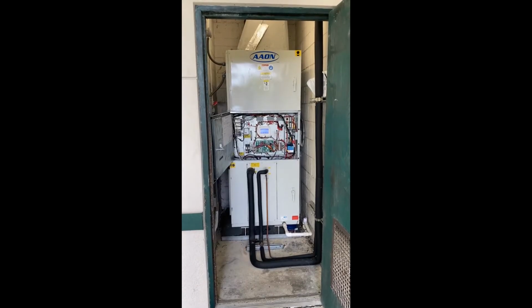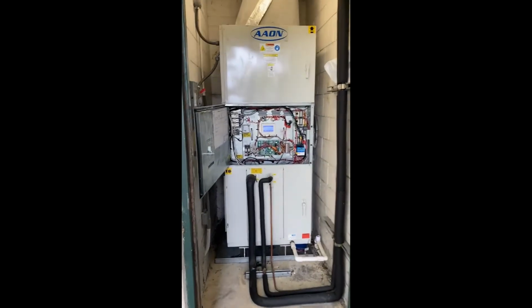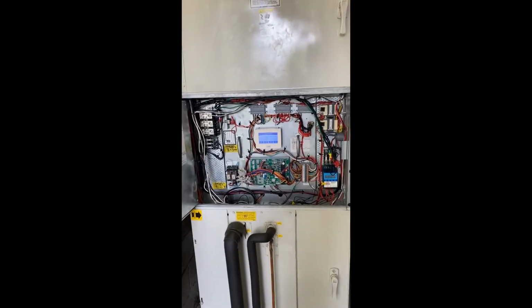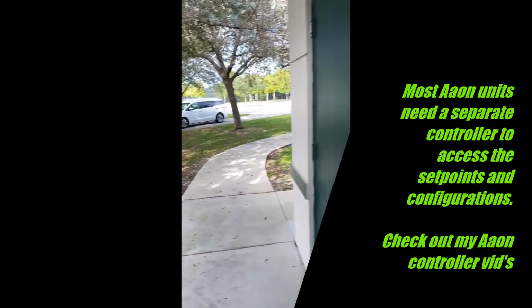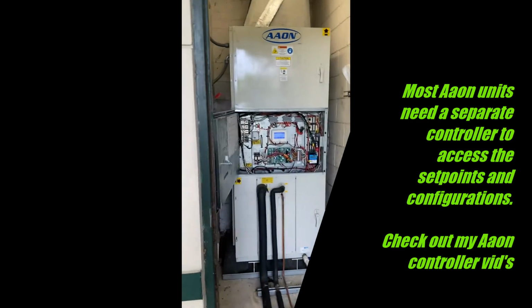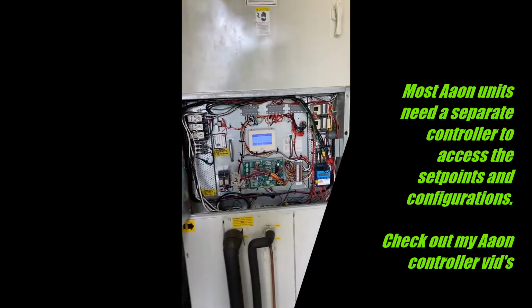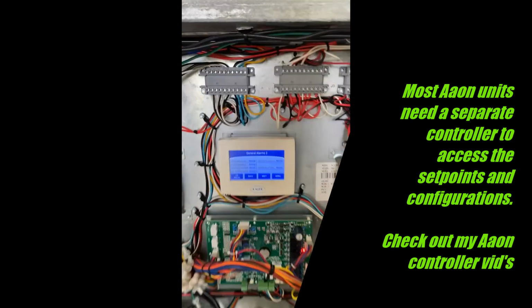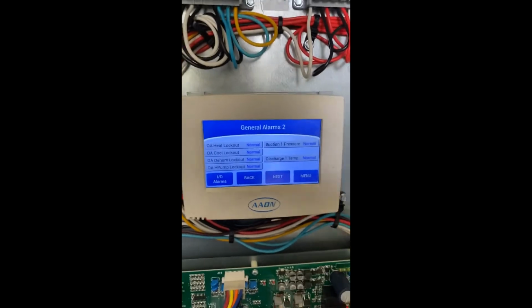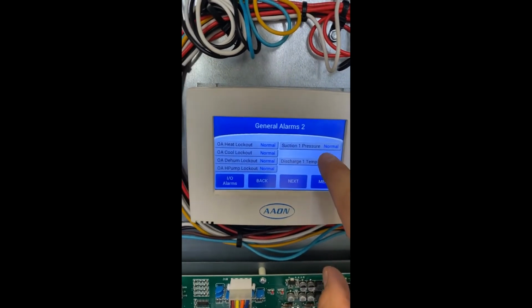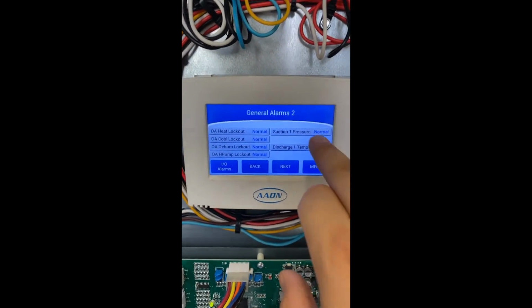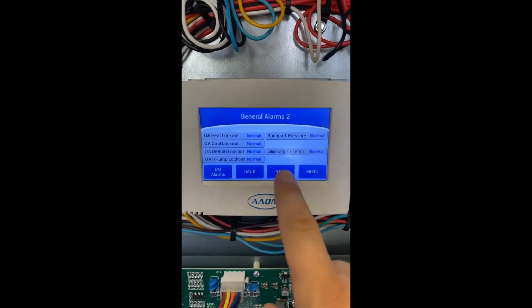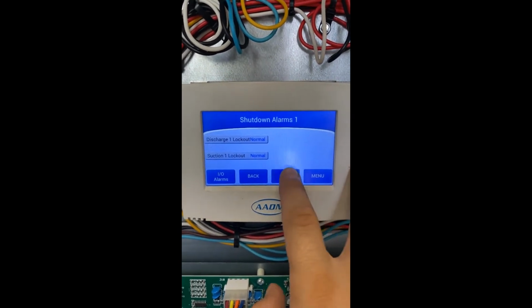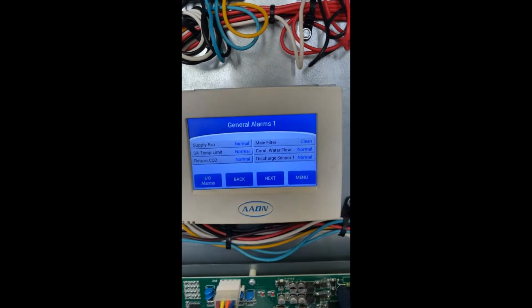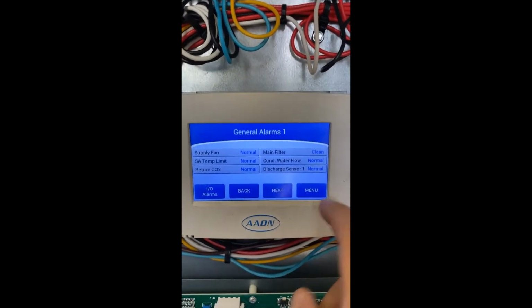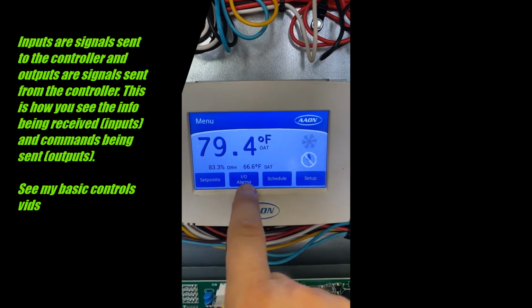Alrighty. So this is the air handler for the AAON split system. These are nice because they have a controller interface. While usually the package units you will need a separate controller to access the set points or configuration. So here we got a nice interface. When my suction transducer was bad, I had a low limit alarm here. It was still blue, it wasn't red or anything, just said low limit. So otherwise it would just say normal. Everything looks normal now. And then we can actually see what our transducer is doing with our in-out inputs.